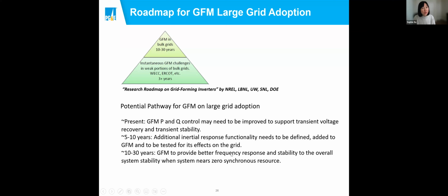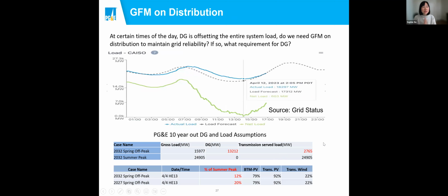And I think a further study probably is needed to see at what point we need to start to interconnect grid forming inverter instead of grid following, because if we keep adding grid following, and at some point most of the system is grid following generation resource instead of grid forming, then another control issue may arise, because 100% grid following cannot stabilize the system. But what about 90%, 85%, things like that? So we need to probably find the tipping point. And before that tipping point, we need to introduce grid forming inverter instead of grid following. So this will be the last page.